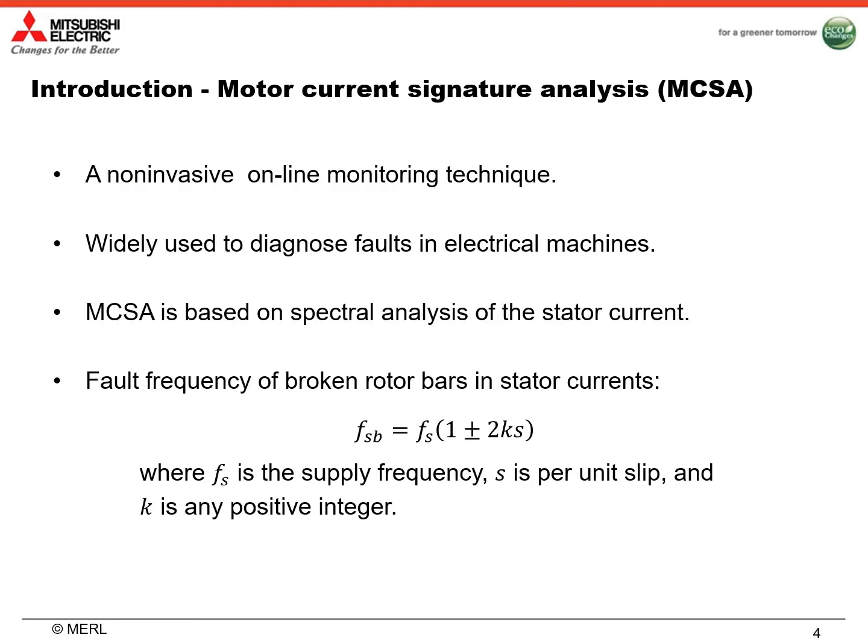Motor current signature analysis, as a non-invasive online monitoring technique, has been widely used to diagnose faults in electrical machines. MCSA is based on spectral analysis of the stator current. If there is a broken bar fault, the stator current will exhibit some characteristic fault frequency components, which can be expressed using this equation. The fault frequency components are a function of the supply frequency, and are also related to the motor slip or motor speed.